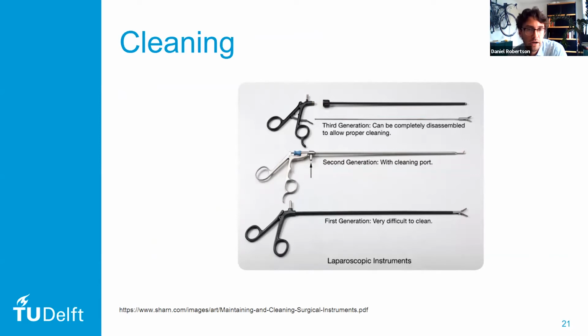So when looking at how to clean the laparoscopic instruments, we have a few different types of instruments. From bottom to top, we have the very first generation of laparoscopic instruments, and these were not really designed for easy cleaning. So these devices make it very difficult to properly clean them. And then we had the second generation of laparoscopic instruments that had a cleaning port fixed onto the device, and this cleaning port made it easier to flush soil out of the instruments. And then we have the third generation, which is the most modern generation. And these are instruments that you can completely take apart so that you get access to all of the surfaces that are required for cleaning.